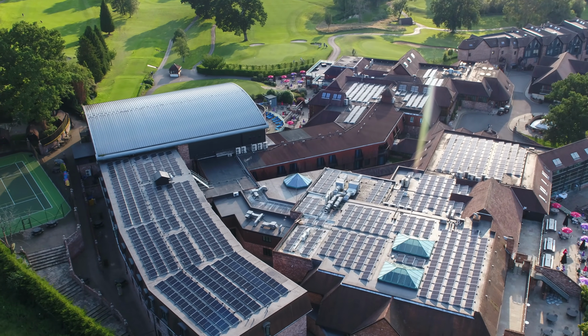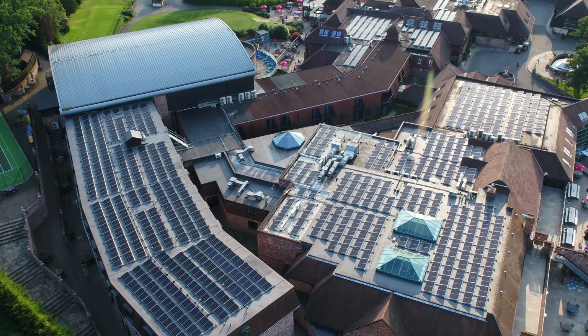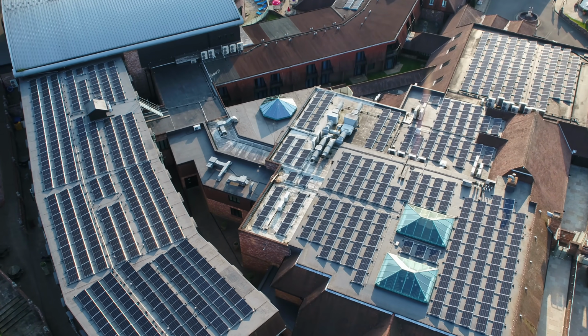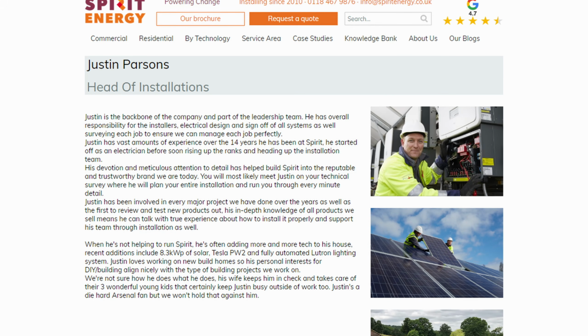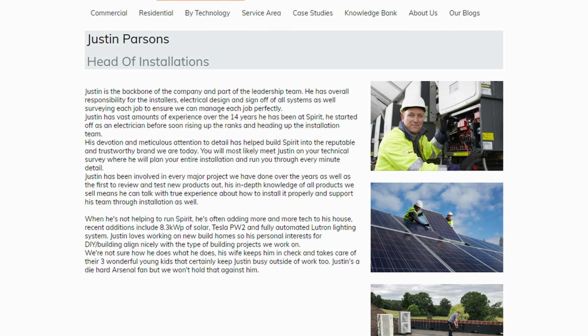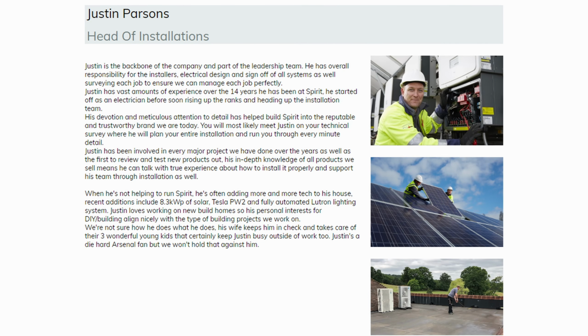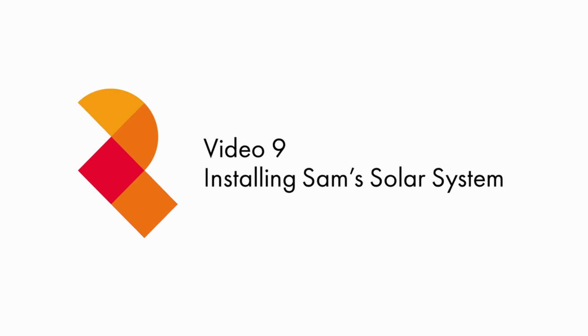Justin also checks that the planned cable run and kit locations are suitable and optimal for the system. This is more relevant for ground mounts or large commercial systems, which can often have very long cable runs, and you do get serious voltage drops if the cables are suboptimally sized. It's important to have someone with 15 years experience look at the system in detail before installation, to make sure the kit locations and cable runs are planned optimally and that the installation will run smoothly and safely. Justin's technical survey is very important to ensuring the job runs efficiently and that everything goes to plan.